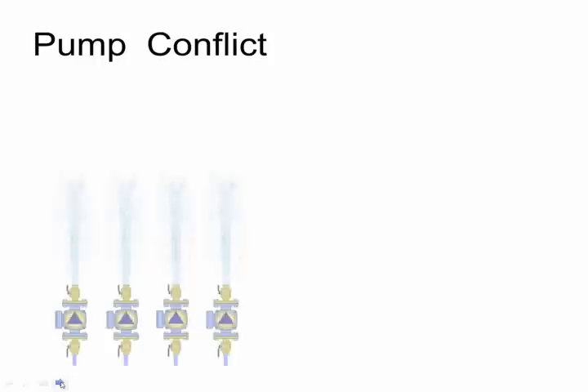Okay, we're going to finish in pump conflict. We're probably going to go 5 minutes late here, but I think it's worth going through. So how do we eliminate pump conflict in a hydronic system? Well, what we want is demonstrated by this graphic. We have a bunch of pumps that we want to have a certain flow rate. And when one pump turns on and one pump turns on, as they turn on and off, we don't want it to affect the flow rate of part of the system driven by another pump. So if that third pump over here, as an example, turns off, the effect that we want is something like this.